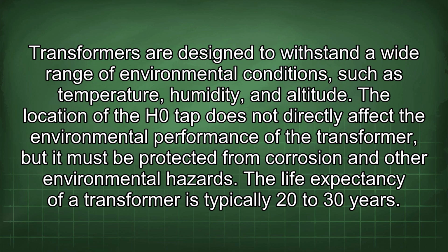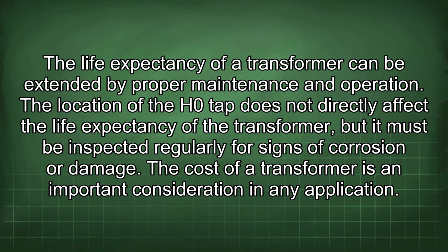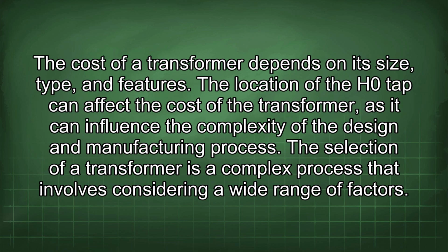The life expectancy of a transformer is typically 20 to 30 years. The life expectancy of a transformer can be extended by proper maintenance and operation. The location of the H0 tap does not directly affect the life expectancy of the transformer, but it must be inspected regularly for signs of corrosion or damage. The cost of a transformer is an important consideration in any application. The cost of a transformer depends on its size, type, and features. The location of the H0 tap can affect the cost of the transformer, as it can influence the complexity of the design and manufacturing process.